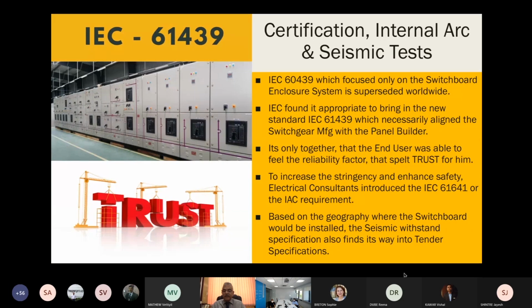It's like what happens when there's a lot of pressure built inside a pressure cooker - the valve goes up and the steam is released. A similar situation has to happen in a switchboard when there's an arc inside. The door should not blow out, but the flap on top of the panel will have to open up and the hot gases need to be released. So is the switchboard capable of doing that? That's what the IEC 61641 test is all about.